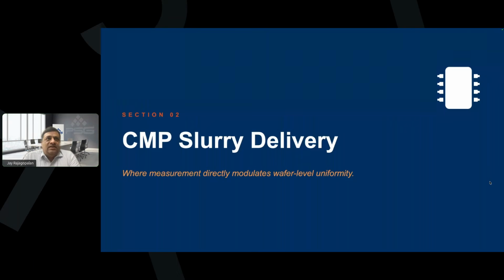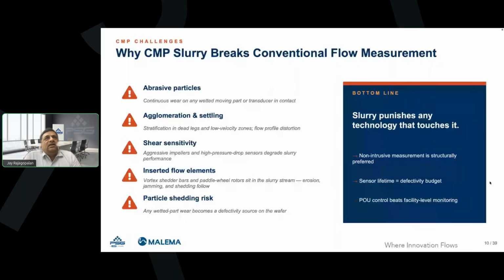First, we'll take the slurry in CMP. CMP slurry really breaks all conventional flow measurement. You see, it has abrasive particles. Obviously, it can lead to wear of different materials that touch it. Agglomeration: if there are any dead legs, the particles can agglomerate into a lump, and then it can cause scratches onto the wafer and hence defectivity.